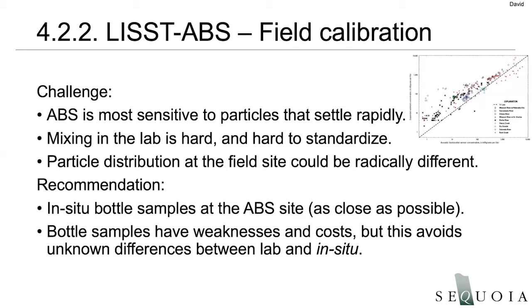Now, of course, the in situ calibration is not simple either. It has its own challenges, and it requires some expertise to do it properly. We consider it best that you have the instrument at your field site in situ, so that it is measuring real particles in a real situation, and that you take bottle samples as high quality as you can, as close as possible to the actual site. Because as you probably all know, the distribution of these larger particles is not going to be uniform within a river or whatever other body of water. It's going to be sensitive to currents and all these other things. And it's going to be more sensitive to those factors than a turbidity measurement. There are weaknesses and compromises and costs in each approach. Basing your calibration on field samples is likely to give you the best, most reliable answers.